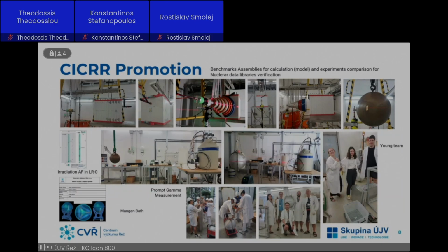This is the case with this high purity germanium detector. This was again in the frame of the open access, which was applied for by the Technical University in Ostrava. They were interested in the prompt gamma measurement from the leakage from the iron, polyethylene, heavy water, and other materials. So we prepared the laboratory equipment for them, and they just brought the high purity germanium detector. We fill it with liquid nitrogen, and they perform the measurement.